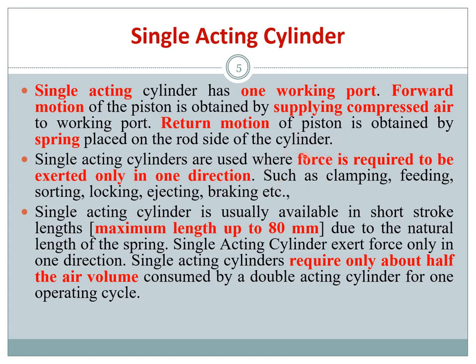Single acting cylinders are used where force is required only in one direction. Applications include clamping, feeding, sorting, locking, ejecting, and braking. They are usually available for short stroke lengths — up to a maximum of 80 millimeters — because this is set by the natural length of the spring.